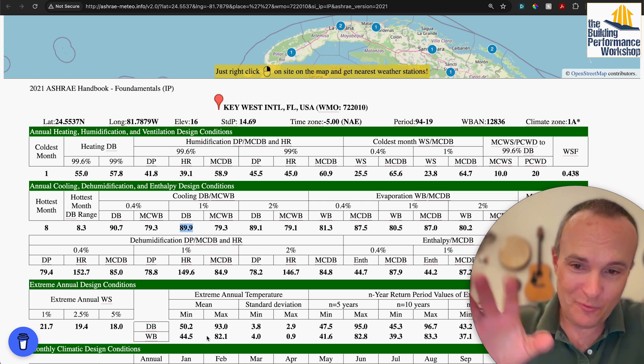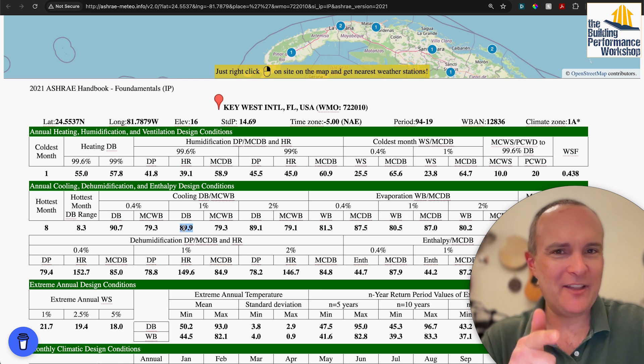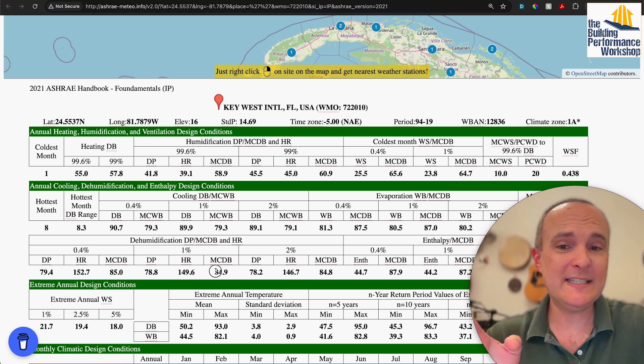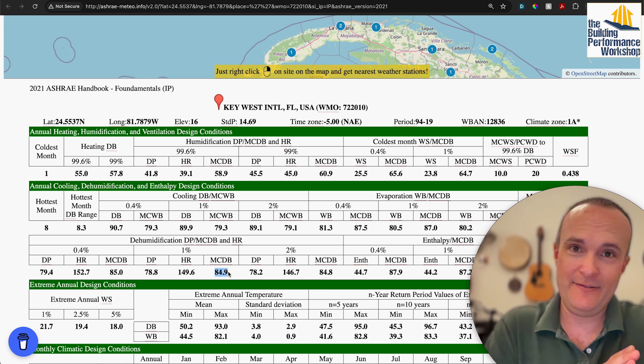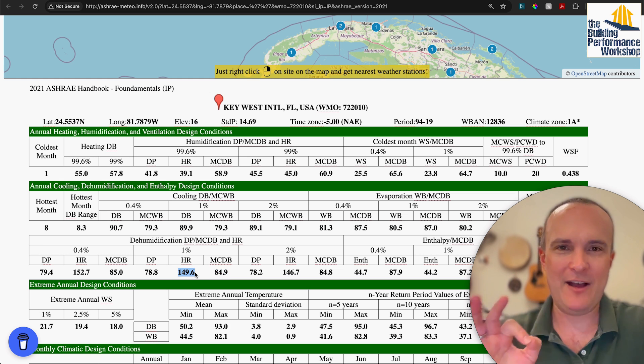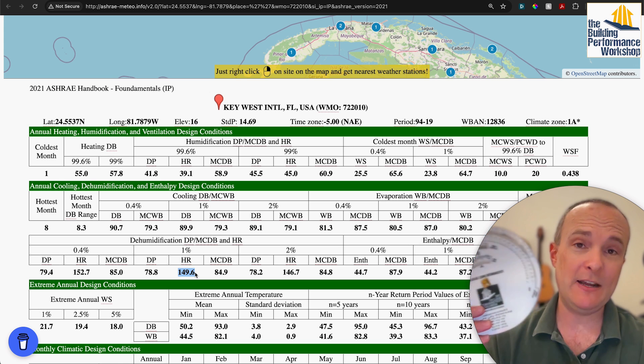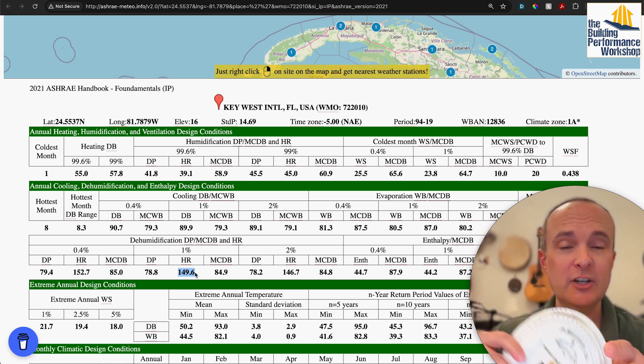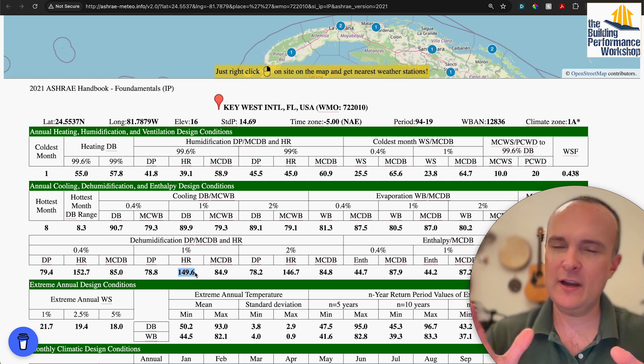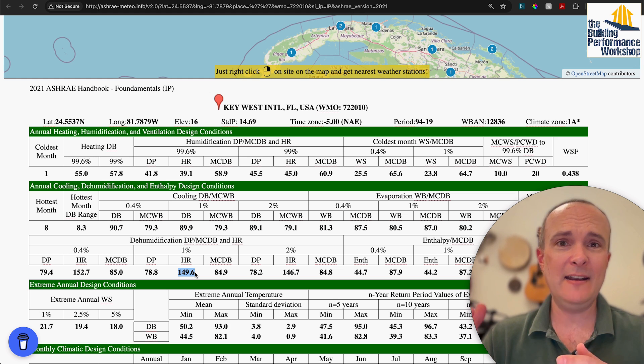We can see that at the hottest temperature, it's not the wettest. The wettest temperature is the dehumidification mean coincident dry bulb. The wettest temperature in Key West is not 89 or 90 — it's actually 85, five degrees cooler. At that temperature we have this many grains per pound of moisture in the air. I use this free download from my website — I'm linking it on screen — because translating between relative humidity and absolute humidity is very important.